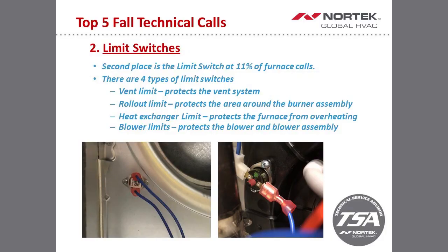And then your blower limits are there to protect your blower assembly. They're also there to protect the furnace when it's in a horizontal left or horizontal right position, to protect the blower assembly. But the main air heat exchanger and the blower limits are going to be an automatic reset. So those snap discs should close once the furnace cools down to a certain temperature. And then if you still have a call for heat, the furnace should then go back through a heat call on that.